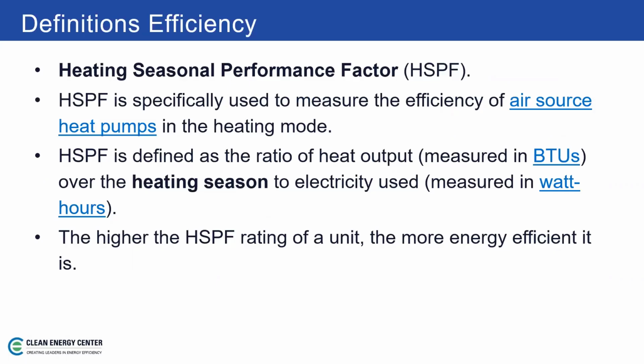So if it's a heat pump, then we also have another rating called Heating Seasonal Performance Factor, or HSPF. That's specifically used to measure the efficiency of air source heat pumps in the heating mode. It's defined as the ratio of heat output measured in BTUs over the heating season to electricity used measured in watt hours. And the higher the HSPF of the unit, the more energy efficient it's going to be.